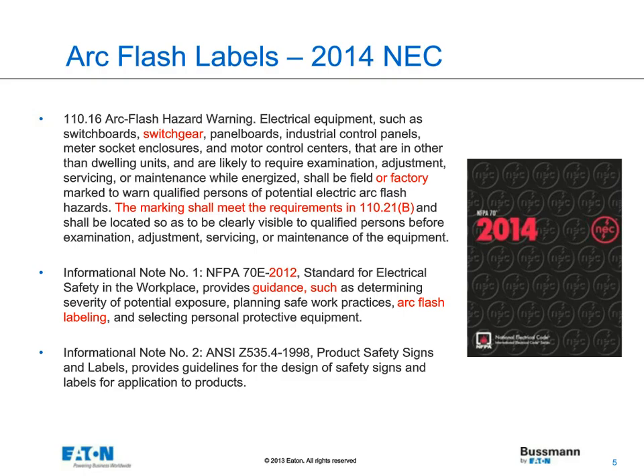The first thing we'd like to talk about is what's required as far as Arc Flash is concerned with regards to the National Electrical Code. As you can see, we have a basic requirement in NEC 110.16. I should mention that anytime I have text in red, as shown in this slide, that represents changes that were new to the standard. One reference I had was for 70E, was 2012. As you'll find out, the current edition now is 2015. But basically, if you look at this section of code, it really just says that we must provide a warning label. We don't actually have to identify the actual hazard for this per the code.